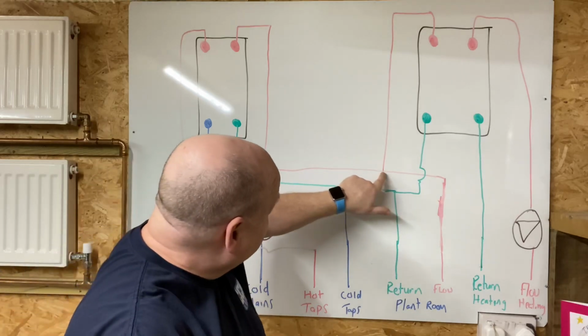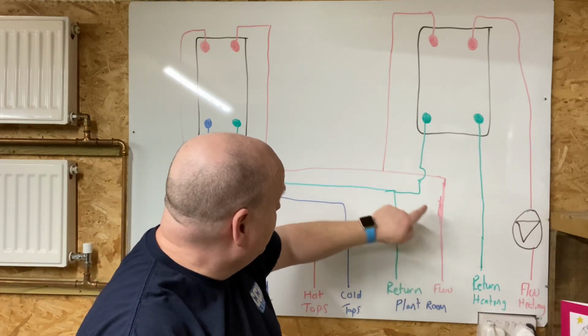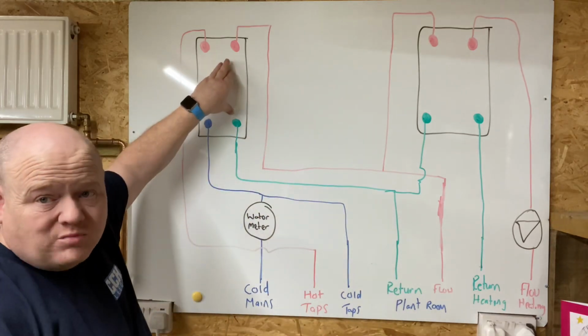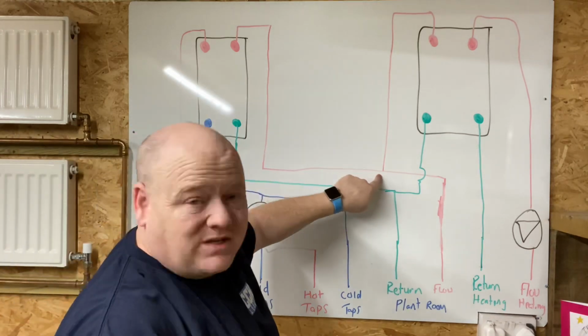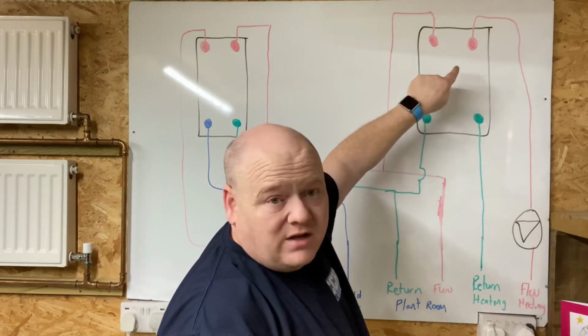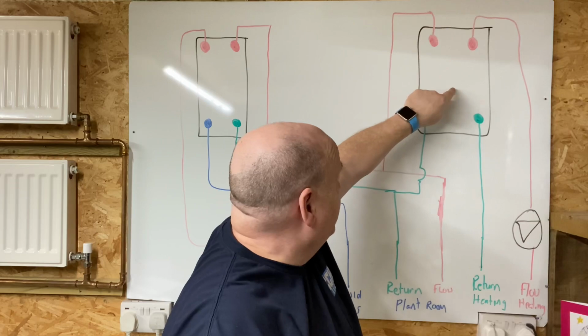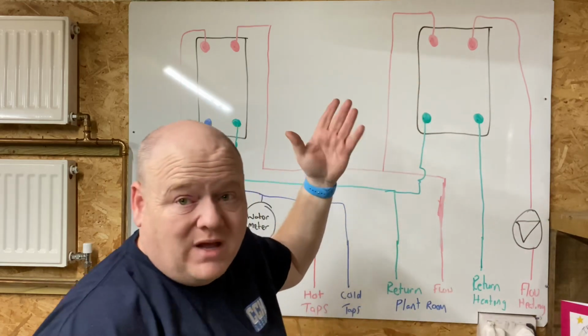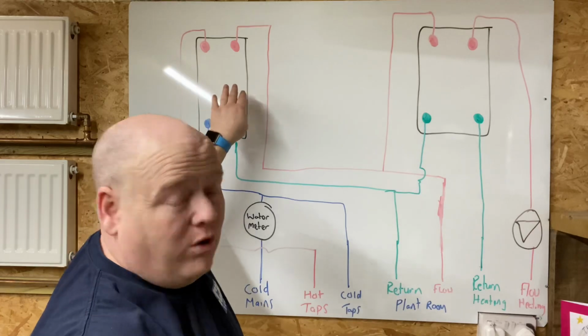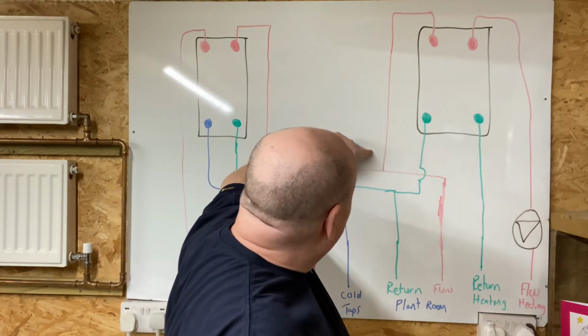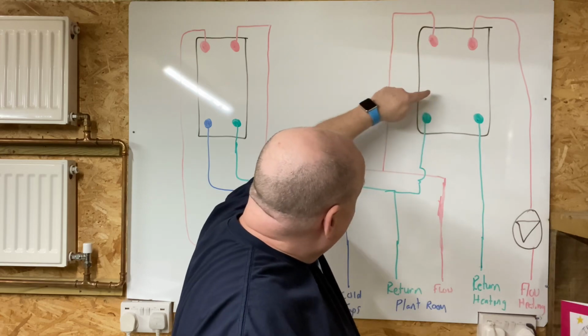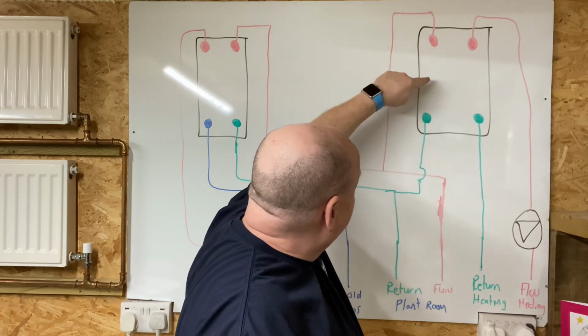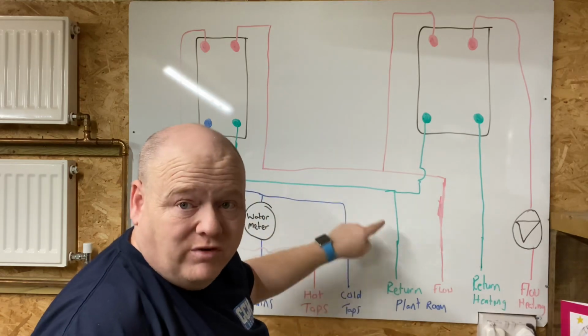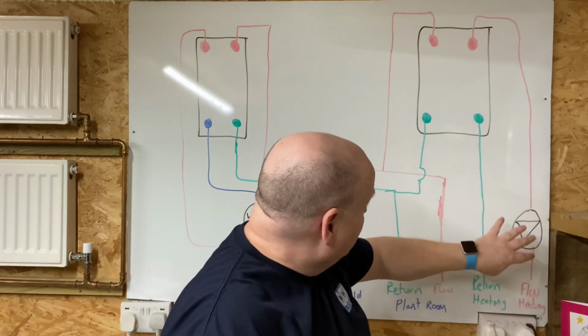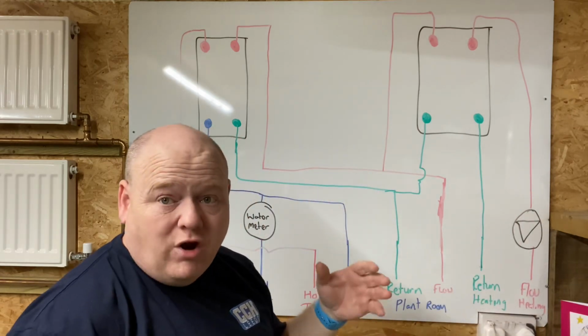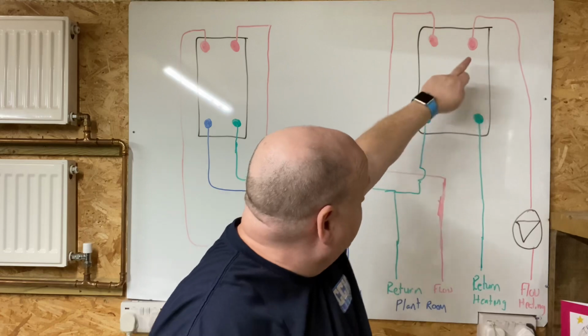But what we've got now, you've got your main flow from your plant room, and one side of it's going to this plate, as we've already spoken about. But then we've got a T on it, and one side of it's going to the heating plate heat exchanger, and that just works identical really to the hot water one. So you've got your main flow going round the plate, cools down because of the water in the central heating system, and then that goes back to the plant room on the return. And then this side of it, all you've got there is just like a normal heating system really. You've got a flow and return into there.